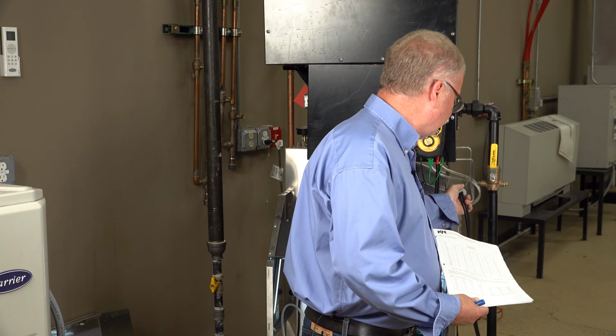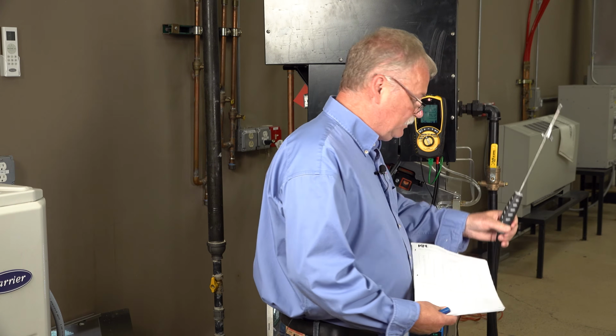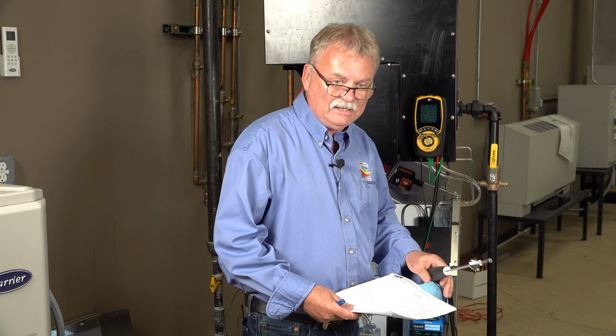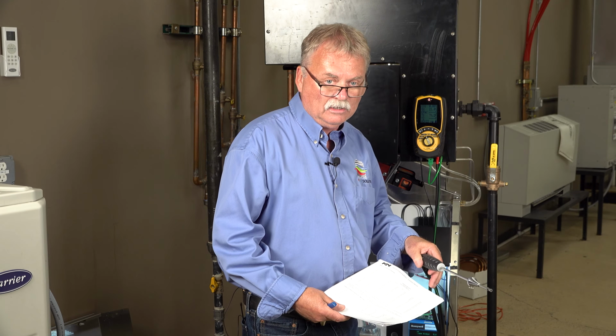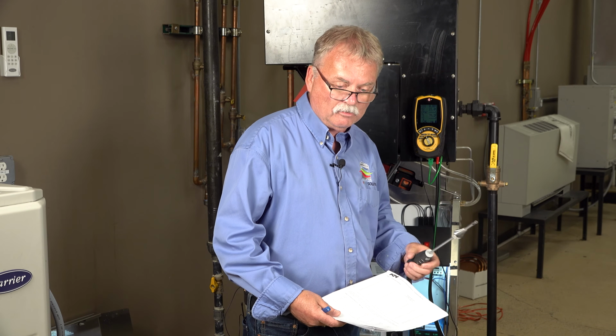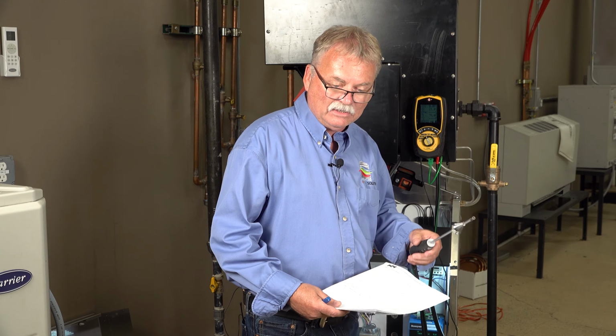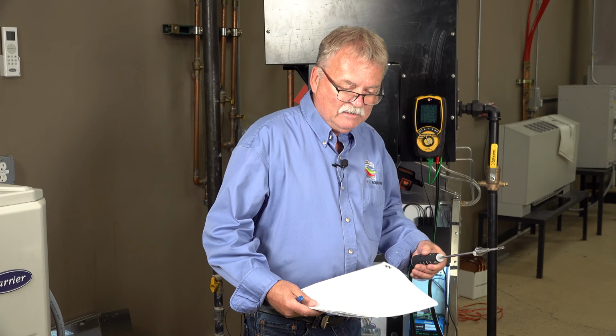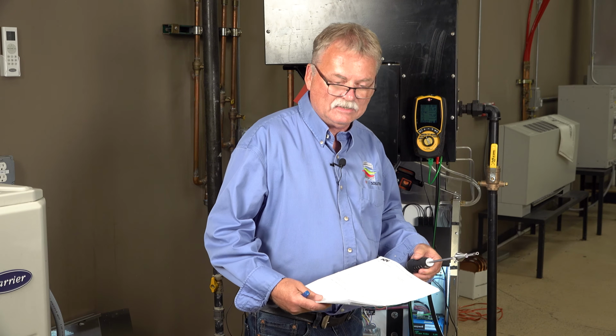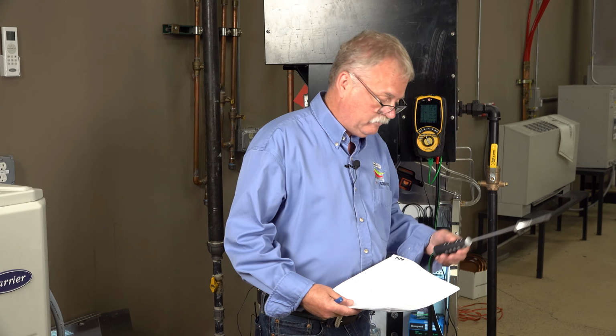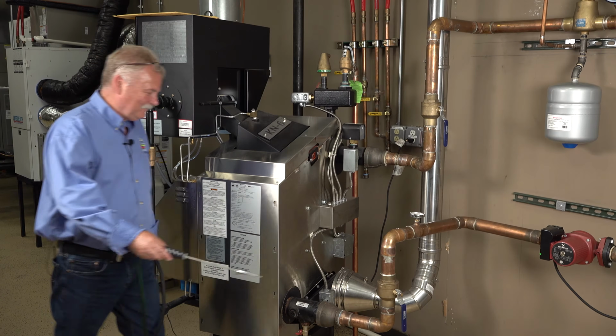Since it fired off, my combustion probe is right here. It was not in the actual boiler when I lit it off. You don't want your probe in the boiler during light off, because light off is an explosive environment. So you're going to have all kinds of gases. You could end up spiking your meter. So don't have your probe in the boiler, in your flue, when you're lighting the boiler off. Now I can put it in.